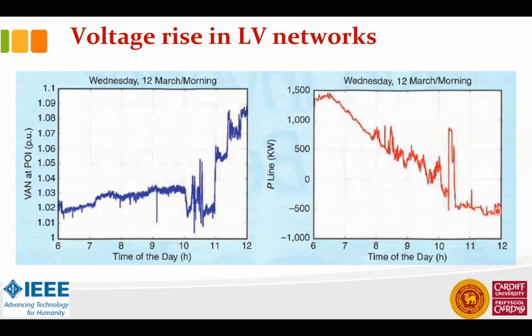So the reverse power flow starts. That means power flows from the houses to the grid. And you can see that when the reverse power flow started, the voltage starts rising. In between, you can see these peaks. They are due to cloud cover. If a cloud comes, power drops to a lower value and you are absorbing from the grid again, and so on. So that will reflect on the voltage also.